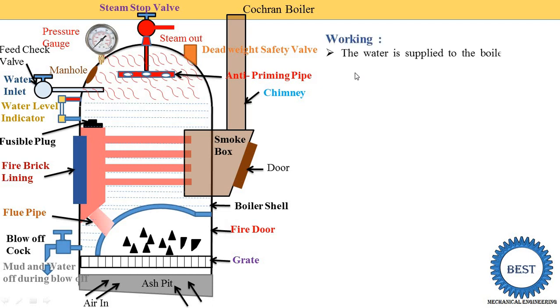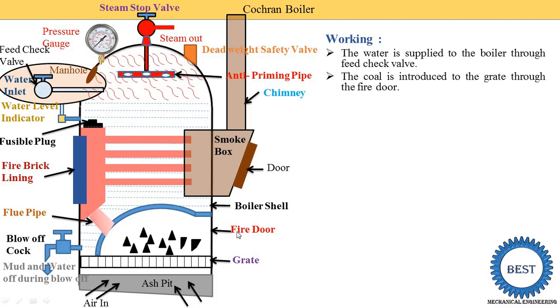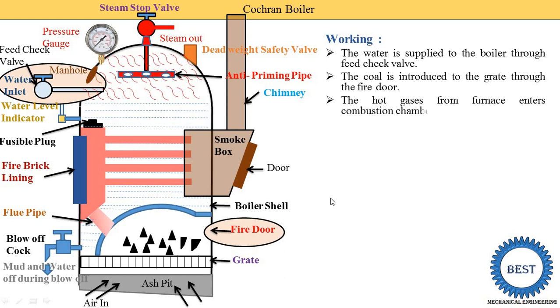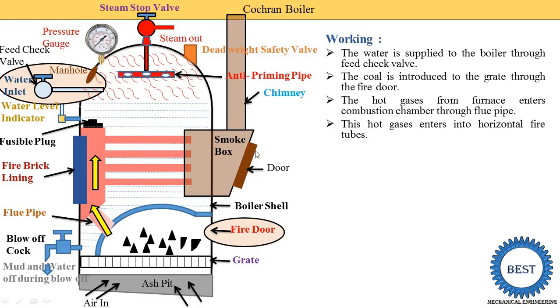Now we understand the working of the Cochran Boiler. In the first step, water is supplied to the boiler through the feed check valve. Second, coal is introduced to the grate through the fire door — coal, oil, or wood can be supplied. The hot gases from the furnace enter the combustion chamber through the flue pipe, where combustion of the coal takes place and hot gases are produced. From the combustion chamber, these hot gases enter the horizontal fire tubes — here we have four fire tubes, though more than four can be used.